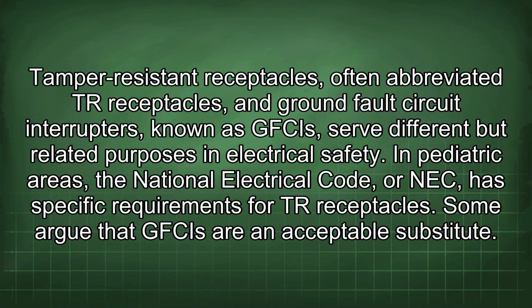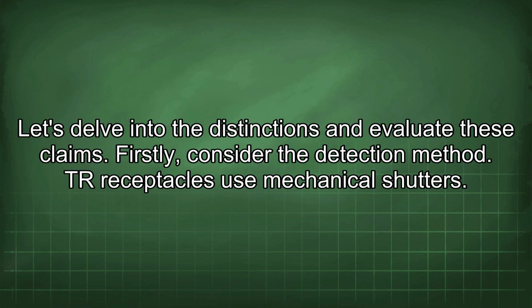Tamper-resistant receptacles, often abbreviated TR receptacles, and ground fault circuit interrupters, known as GFCIs, serve different but related purposes in electrical safety. In pediatric areas, the National Electrical Code, or NEC, has specific requirements for TR receptacles. Some argue that GFCIs are an acceptable substitute. Let's delve into the distinctions and evaluate these claims.